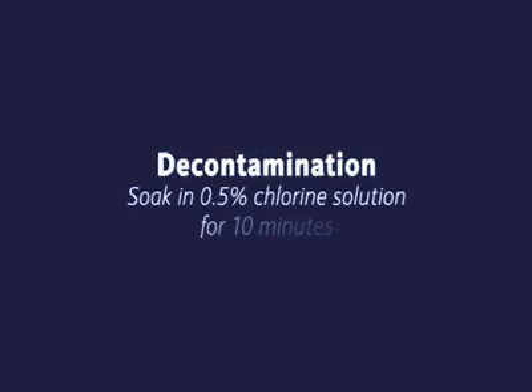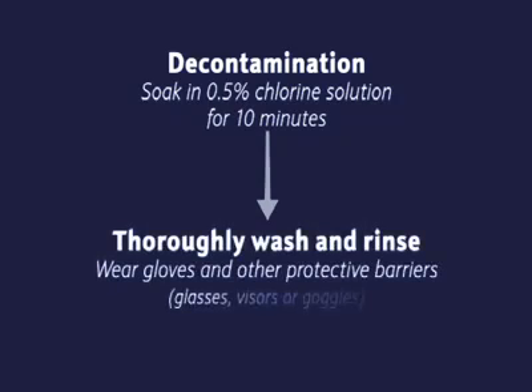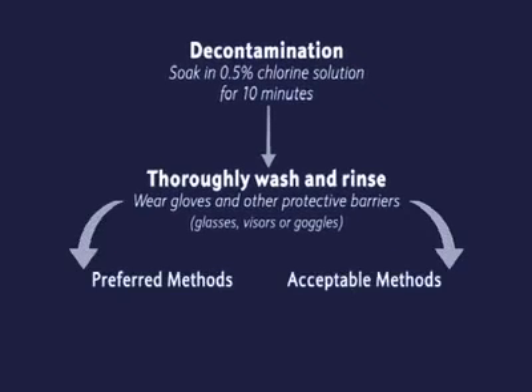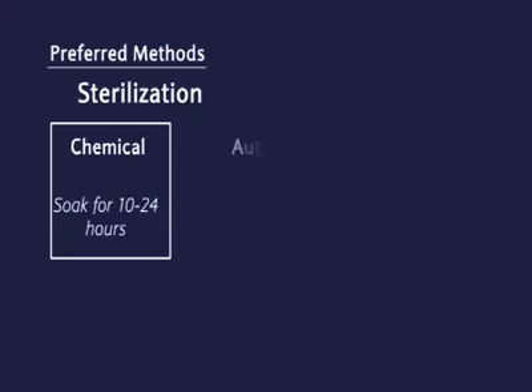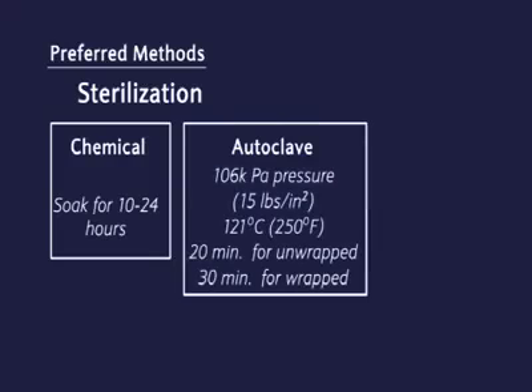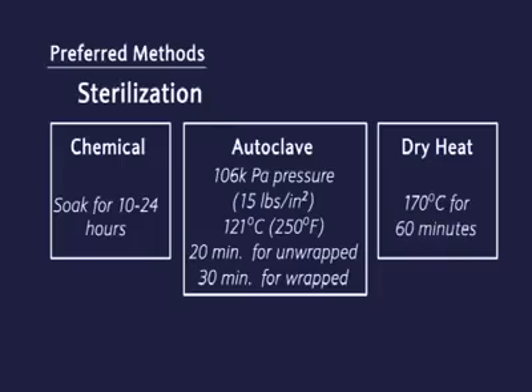Decontamination. Soak in 0.5% chlorine solution for 10 minutes. Thoroughly wash and rinse. Wear gloves and other protective barriers like glasses, visors or goggles. Preferred methods. Acceptable methods. Preferred methods. Sterilization. Chemical. Soak for 10 to 24 hours. Autoclave. 106 kilopascal pressure, that is 15 pounds per square inch. 121 degrees centigrade, that is 250 degrees Fahrenheit. 20 minutes for unwrapped. 30 minutes for wrapped. Dry heat. 170 degrees for 60 minutes.